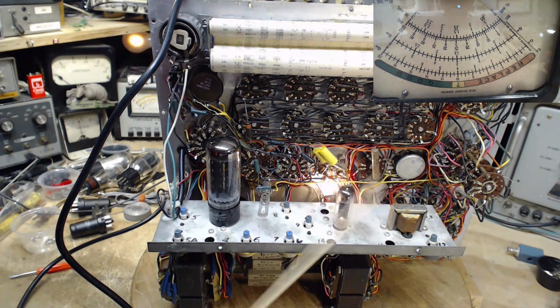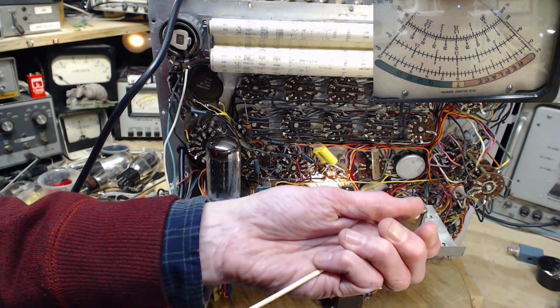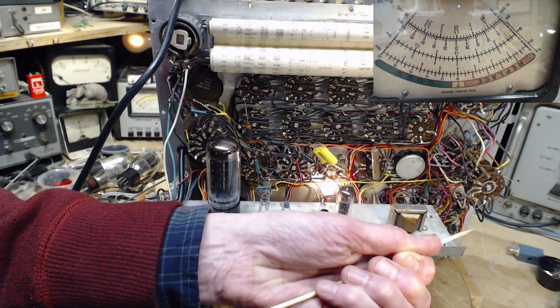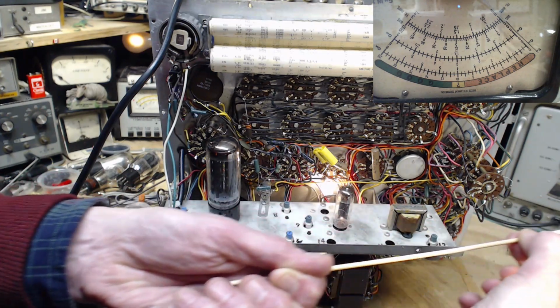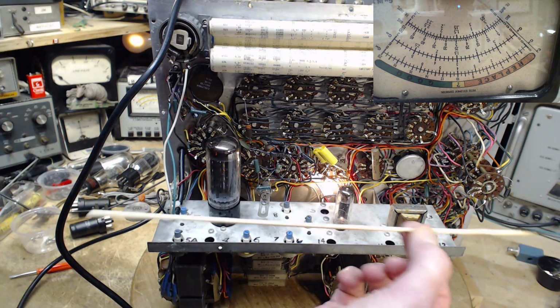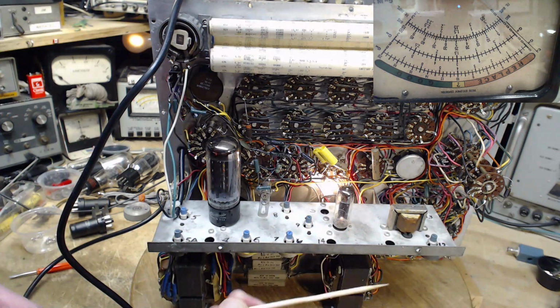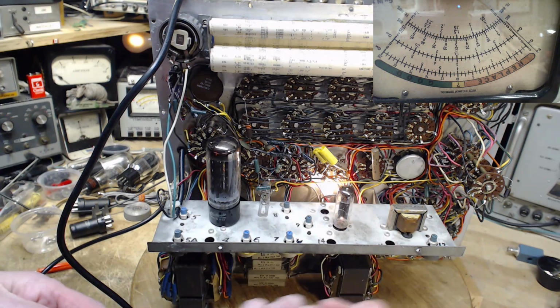Making the old lead cable with the paper tapes on it was a very, very difficult process. But there are ways to make plastic insulated cable where you just put the conductor through a die and squeeze the plastic onto it. Out she comes, all done - well, not quite all done, but way cheaper. So there was huge interest in industry to come up with a cable where you could just extrude plastic insulation on it.